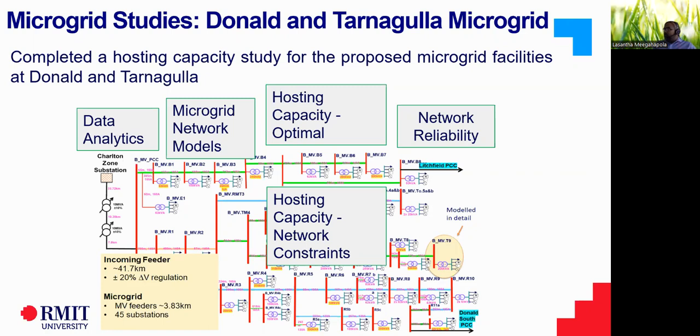There are two different towns, and those two towns have different specifications. So we have done a completely technical study to analyze the feasibility of islanding those two towns from the main grid and operating them as microgrids. We have seen a clear-cut potential there as well, but still a clear-cut business case should be developed, and the funding should be secured to implement these microgrids. This project, in fact, we did with C4NET, one of the organizations which run these sorts of community projects, and several other partners were also involved.